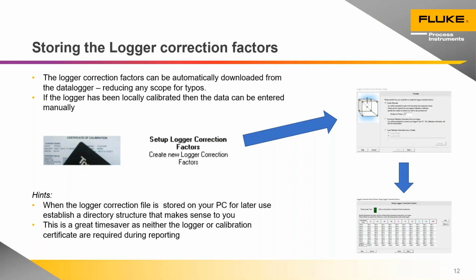If the data logger has been calibrated by a third party, so typically an in-house calibration service or lab, the calibration will not be stored in the data logger. And in that case, the software wizard, you can see in the screenshot on the bottom right, allows you to enter the set points and to enter the calibration data so that that correction file can be stored. It's always worth doing this when the logger comes back from calibration, storing the results on the PC.